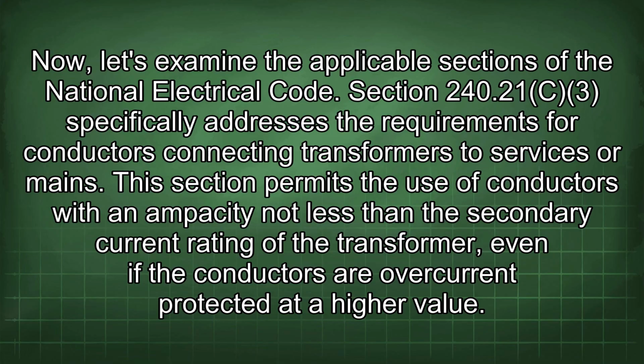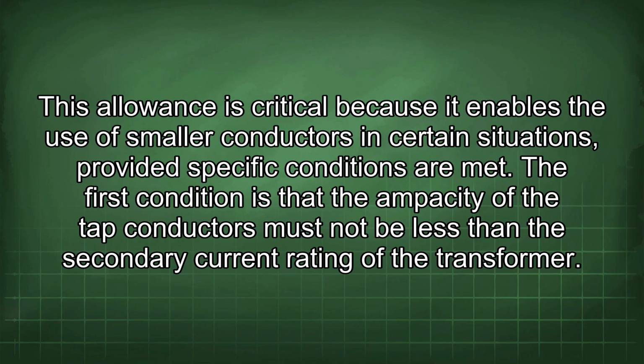Section 240.21(C)(3) specifically addresses the requirements for conductors connecting transformers to services or mains. This section permits the use of conductors with an ampacity not less than the secondary current rating of the transformer, even if the conductors are overcurrent protected at a higher value. This allowance is critical because it enables the use of smaller conductors in certain situations, provided specific conditions are met.